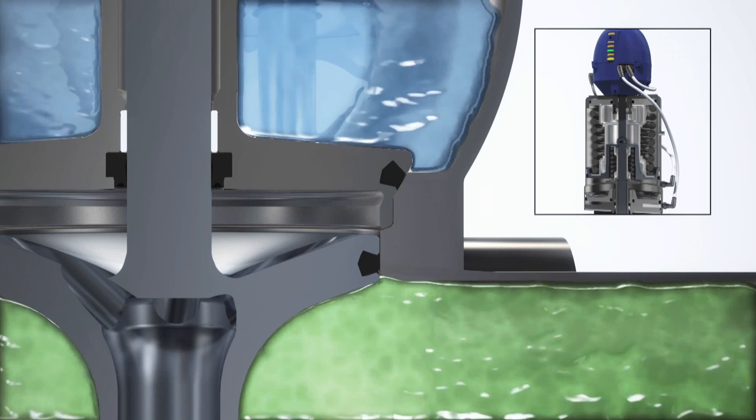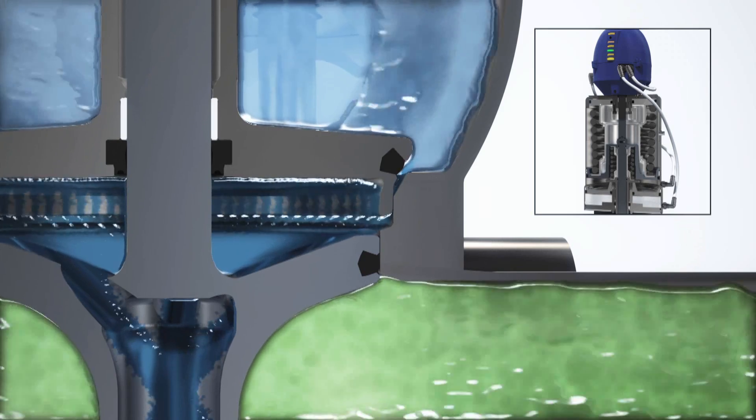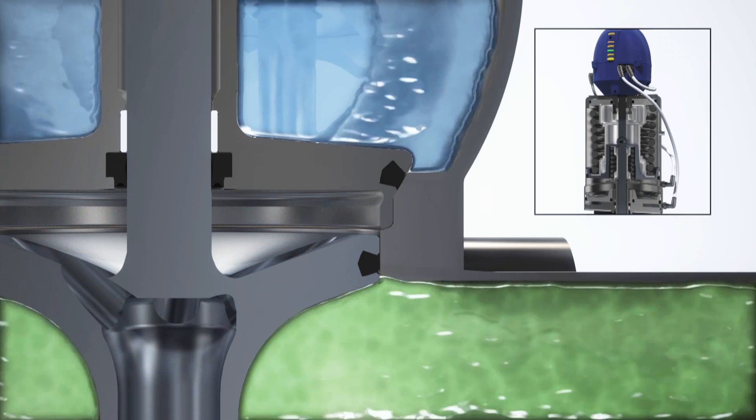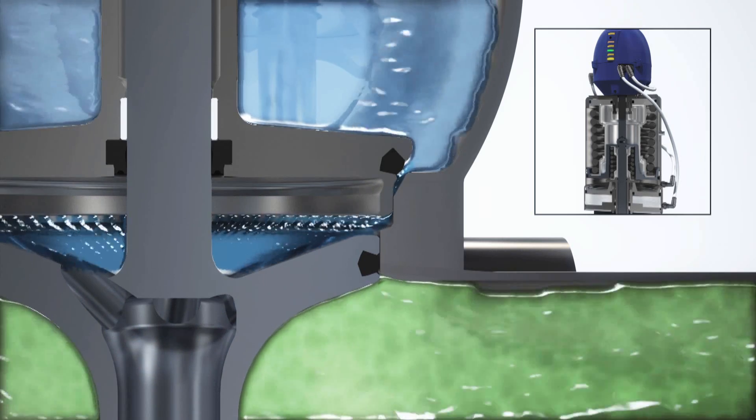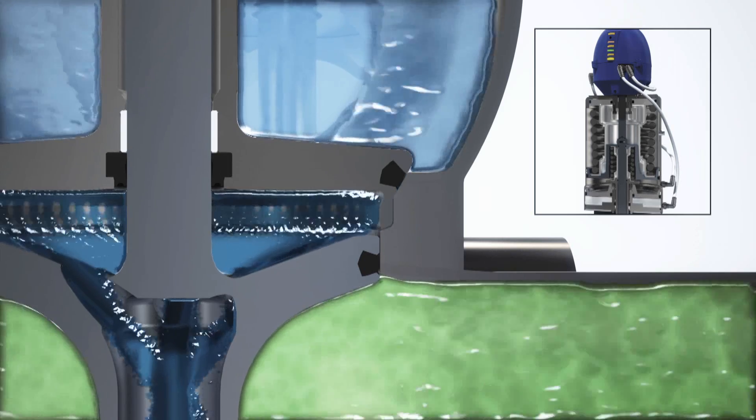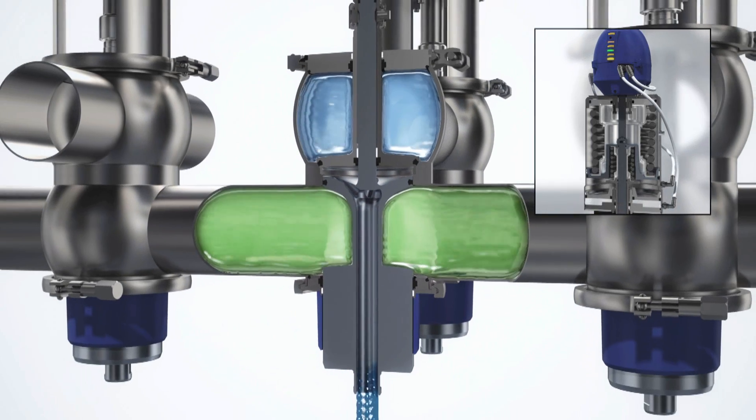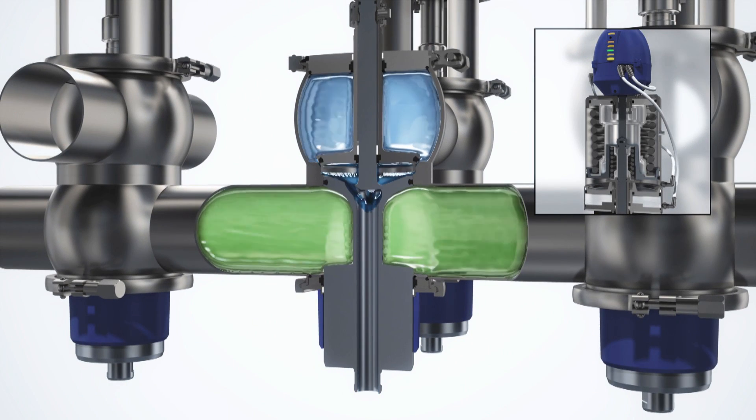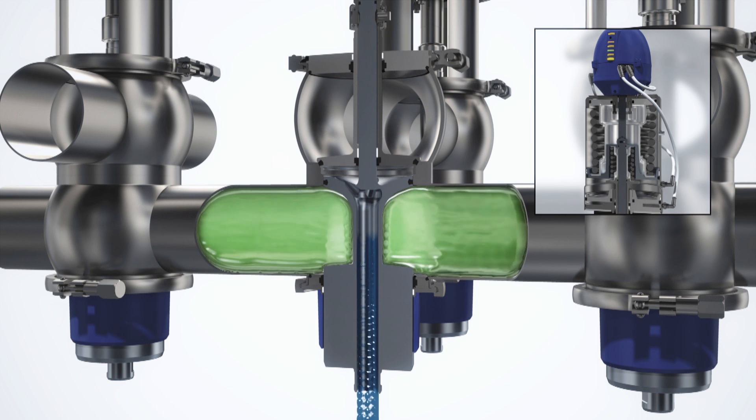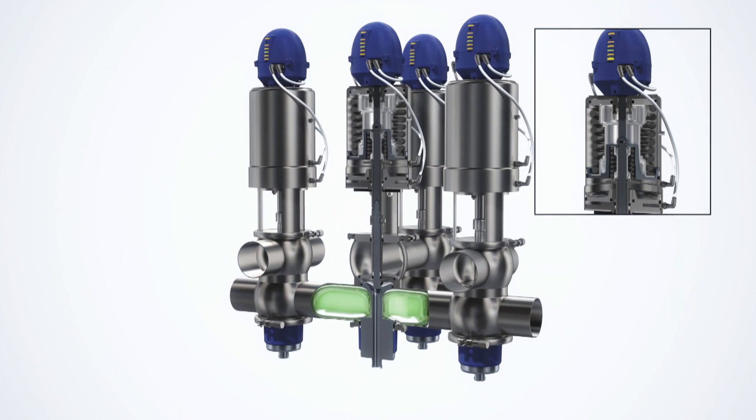This speeds up the cleaning process by creating high turbulence and scrubbing effects, making very efficient use of a minimal amount of CIP fluid. It also reduces pressure of the CIP fluid, eliminating the risk of pressure build-up in the leakage chamber and ensuring risk-free cleaning.